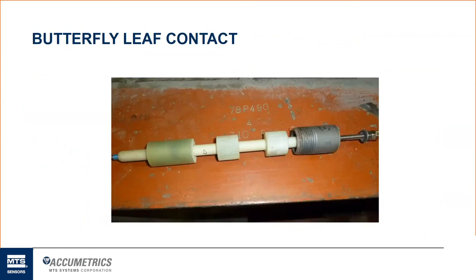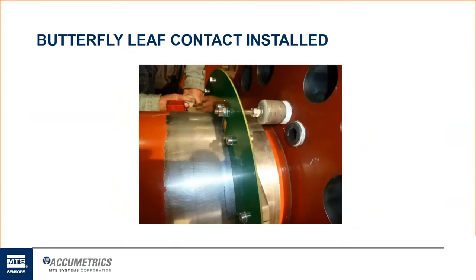We then will cover our stainless steel threaded rod in this fiberglass material to prevent any risk of voltage breakover to the coupling flange bore itself, which would obviously be field ground or metal steel of the machine. So these pieces will offer strength and will be a tight fit inside that bore to prevent any bending or warping of our threaded rod, and then the more narrow pieces are just covering it to prevent the isolation from voltage break. And then it just gets threaded in with this pipe thread piece on the end, and that shows an example of how we install that into the coupling flange on the larger. Again, this is for the larger, typically hydrogen cooled Westinghouse machines, is how we do the connection for the negative and positive side of the field.